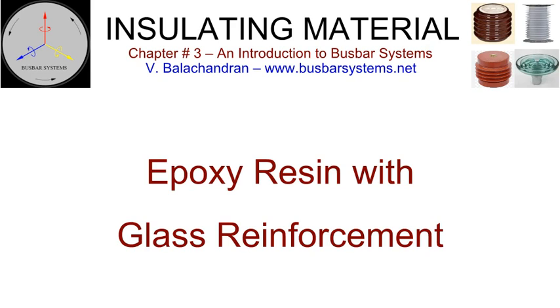The process comprises a large number of glass filaments passing through a mix of epoxy resin and hardener and converging to a profiled mold and pulled at the other end. Glass-reinforced epoxy resin components are used in busbar systems as support blocks, bushings, phase barriers, and tie rods.